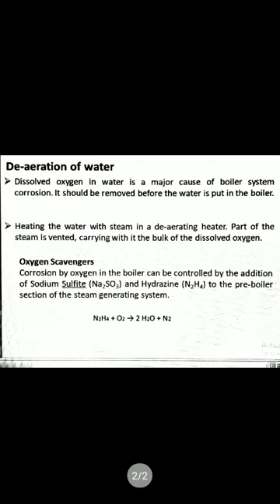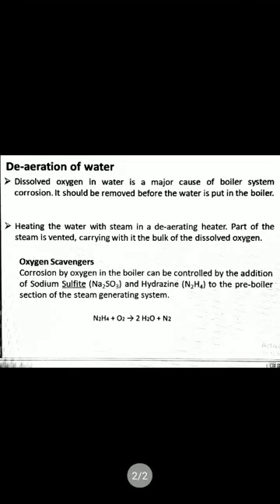The last process is deaeration of water. Dissolved oxygen in water is a major cause of boiler system corrosion and should be removed before the water is put into the boiler. Heating the water with steam in a deaerating heater, part of the steam is vented, carrying with it the bulk of the dissolved oxygen. Corrosion by oxygen in the boiler can be controlled by the addition of sodium sulfite and hydrazine to the pre-boiler section of the steam generating system. The reaction is: N2H4 + O2 → 2H2O + N2.